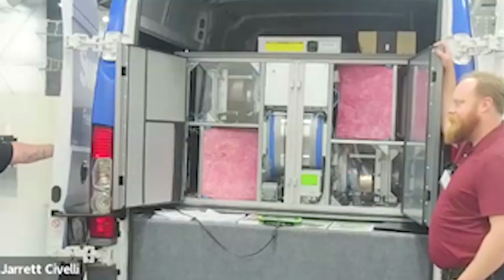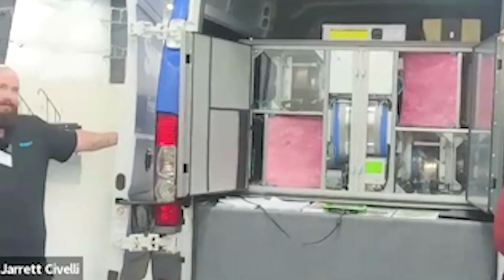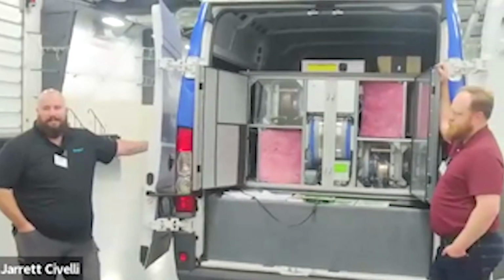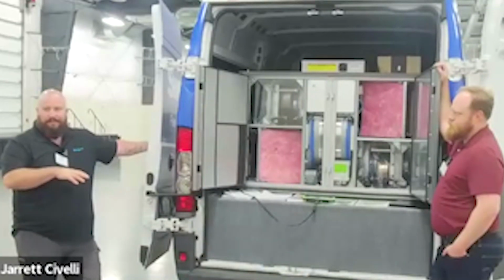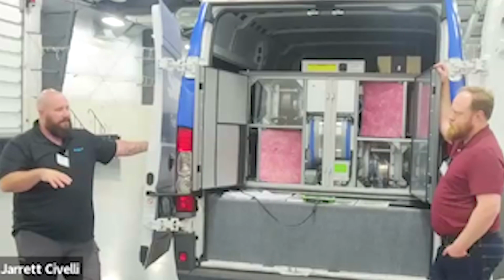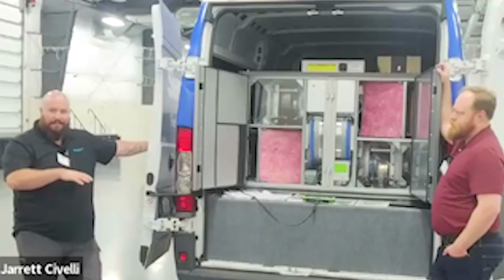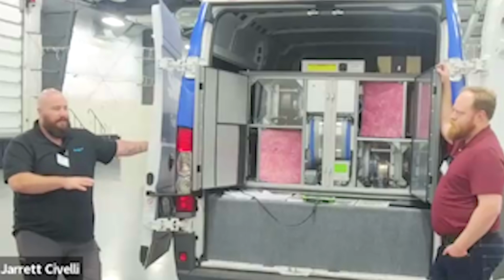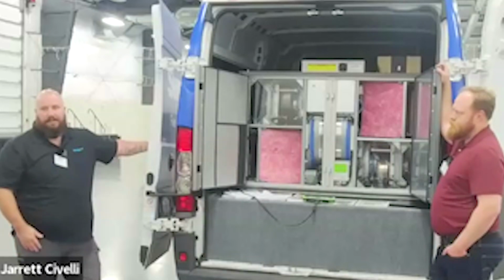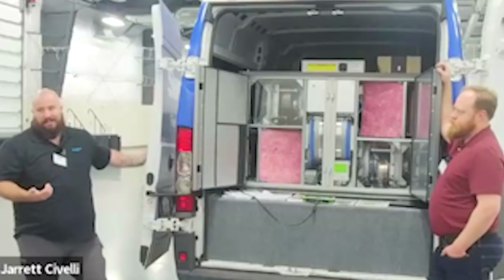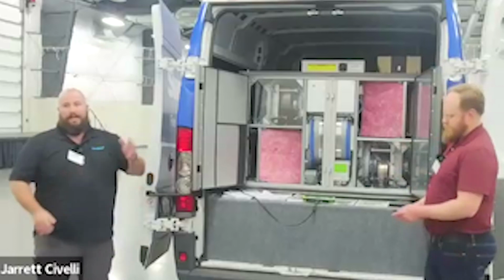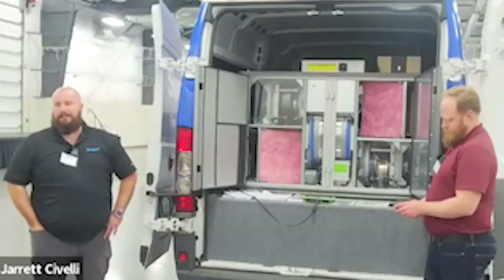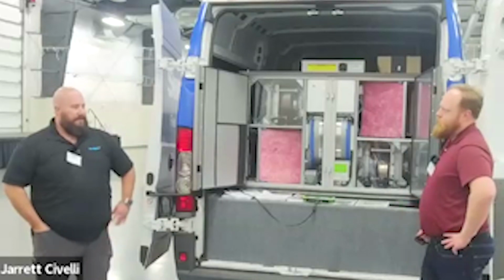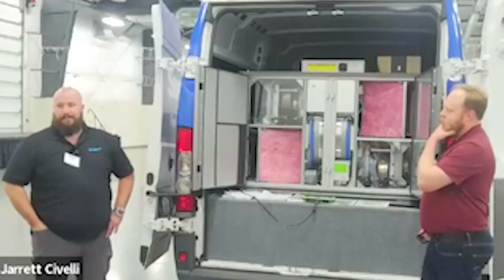As a whole, on the topic of energy recovery, I'm a huge believer. I came from Spokane Public Schools, the second, now third largest school district in Washington. Looking at House Bill 1257 in Washington, we were calculating EUIs for different buildings. It was easy to see that buildings with energy recovery were meeting our EUI, which is your energy use index, based on cost per square foot. Buildings that didn't, that had just standard gas-fired makeup air units, were way over and were going to end up costing the school district money. So it's a worthwhile technology - I think it really saves folks money.